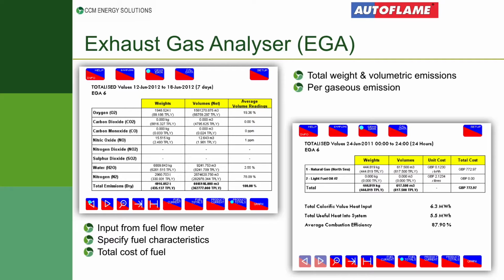And this will tell you here your totalized value between this date and this date, which is what you've selected, give you your oxygen, carbon dioxide, NOx, SOx, water, nitrogen, all of your emissions that have been going up the stack. Obviously, the important one here is our carbon emissions. It'll tell you in that period of time, what is your weight and tonnage of carbon that you've been emitting from that boiler.